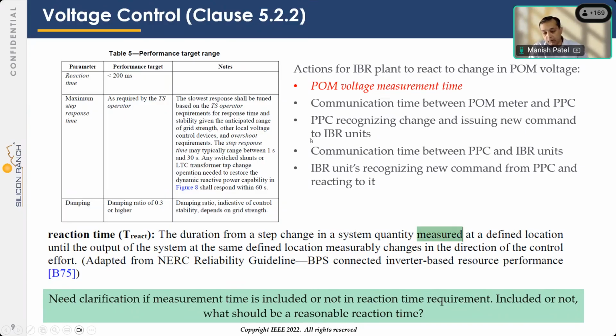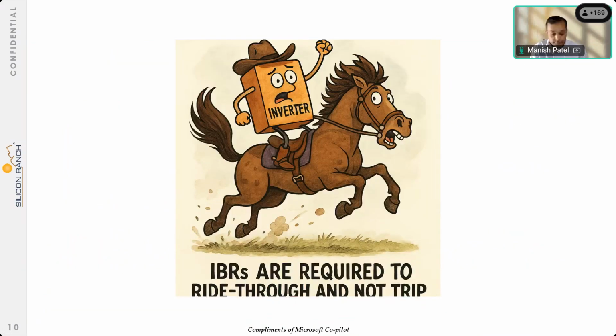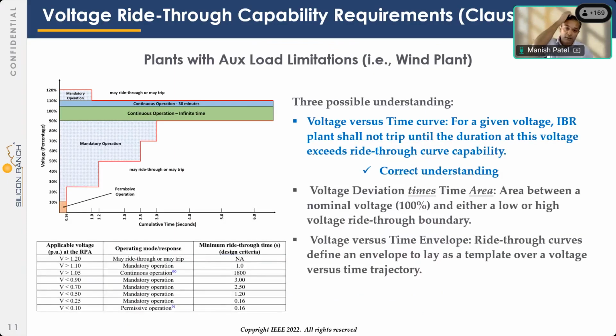That same thing applies. There is another requirement in the standard for fault current injection, which has a step response time. And there also, the time that we agreed in the standard included time for measurement and a change of a control quantity, right? So anyhow, we need to make sure this is all kind of cleared up in the next revision. All right, ride-through. IBRs have to ride through. I agree. I think it does not make sense for IBRs to go offline for a three-cycle fault on the system. But I think this ride-through word is so powerful, and I personally feel that we missed the boat a little bit in understanding what we mean by ride-through requirements. So in the standard, you will see a figure like this in the annex, a table like this in the main body of the standard.